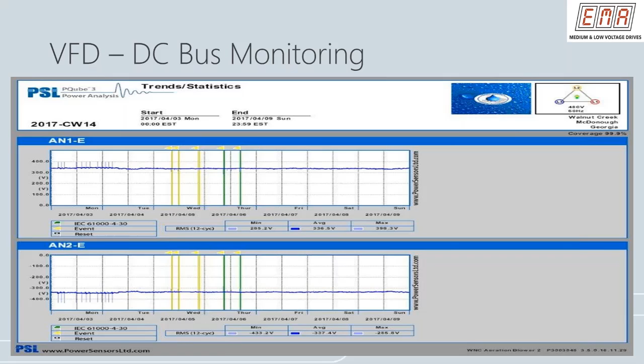One of the things I told the customer is, if we had sent a service guy, one of our engineers, to go look at this problem, chances are they would not have been able to find it, because they'd put a scope on the drive at some point in time and it would come back clean, not seeing anything. However, because DriveScan is continually recording this data, we're able to see every minute - it's sampling every 30 milliseconds. So we can see what happened last week, two weeks ago, or even a year ago.